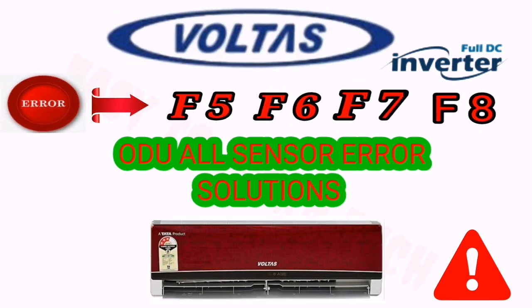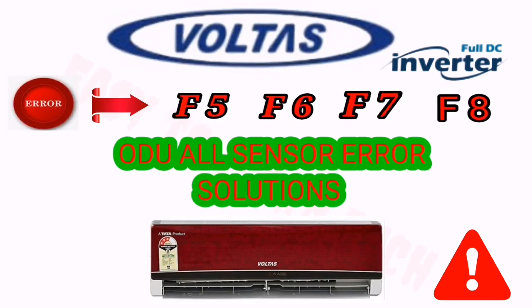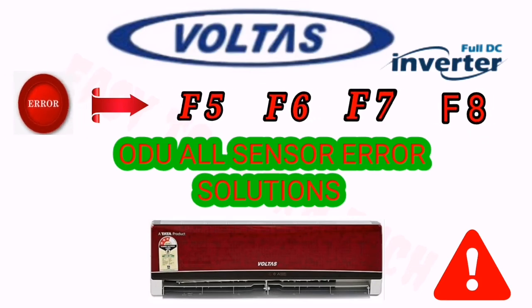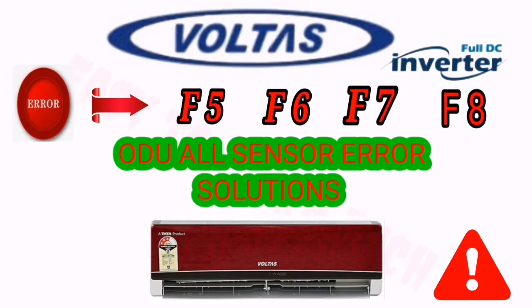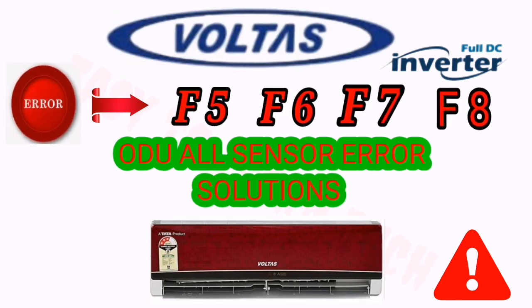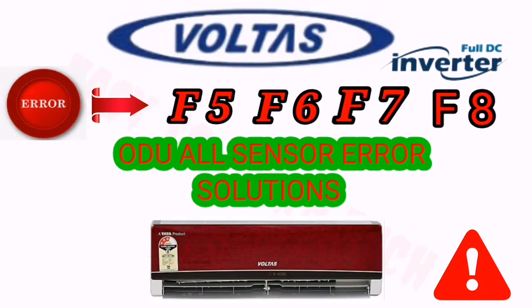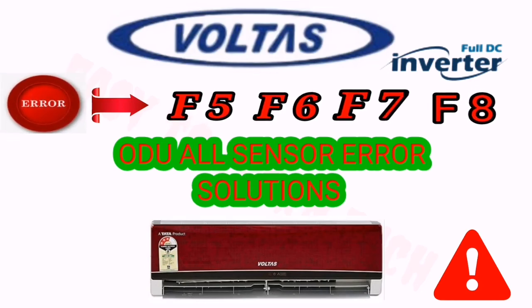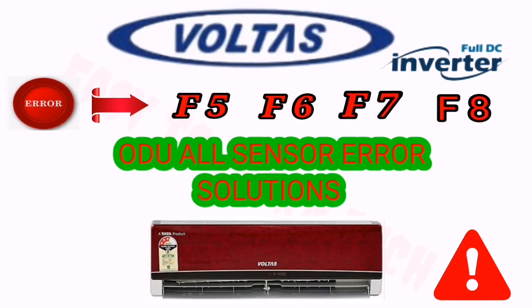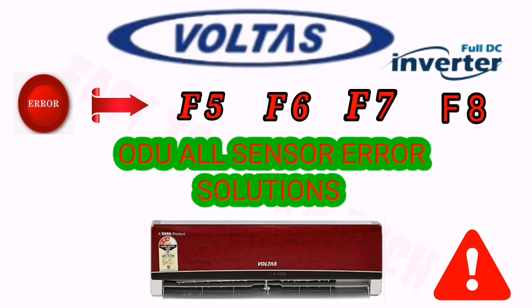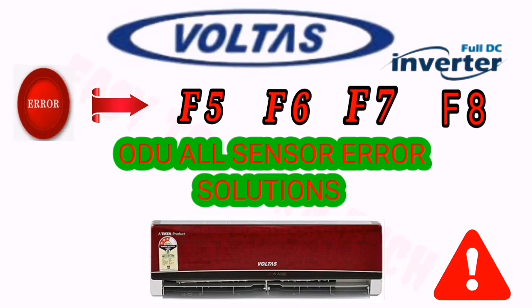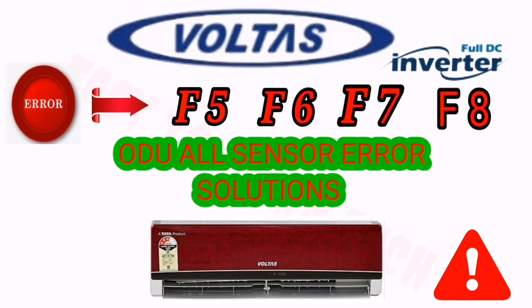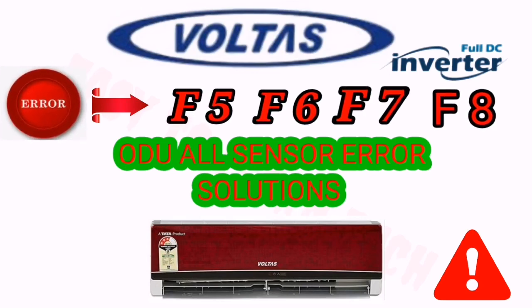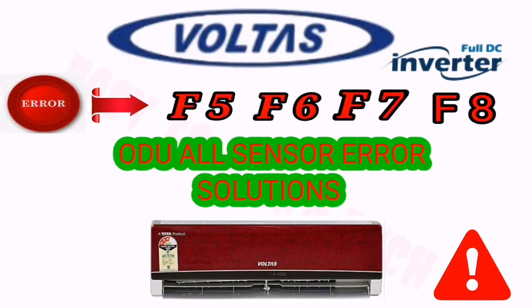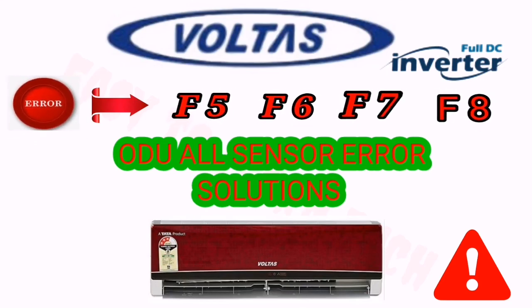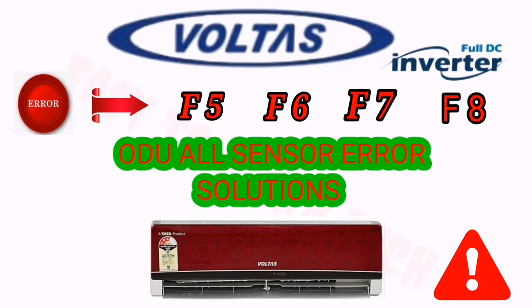First of all, you have to check the placement of the sensor. Then you have to check the connection in our outdoor PCB, whether it is properly connected or not. If it is not connected, connect it properly and start the unit. And again, if you get any error out of these four, then you have to check the wire between our outdoor PCB and the sensor, whether it is cut or damaged or not. If it is not damaged, then you have to restart the unit and check again. If it's showing the same error, then you have to check the resistance of the sensor. If the resistance is okay, then you have to check the output power supply coming from our outdoor PCB. If the output power supply is not coming properly, then you have to change the outdoor PCB, and if the resistance is not good, then you have to change the sensor and your unit will be in working condition.